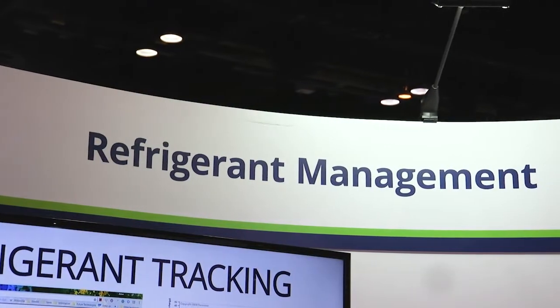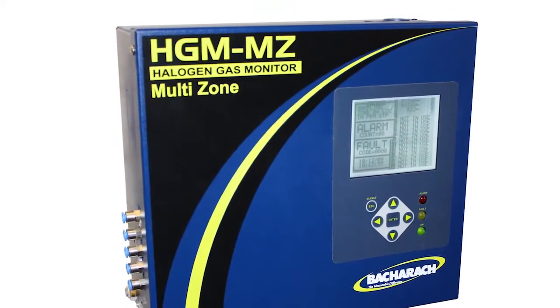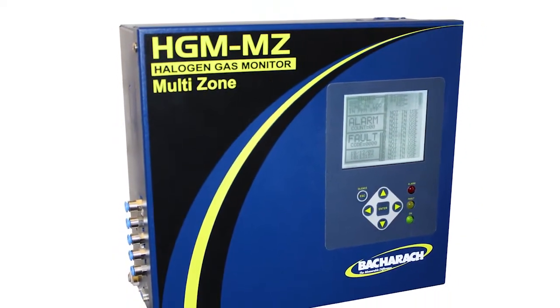I'm Tom Berniston, Bacharach's product manager for our refrigerant leak detection products. I'm here to talk to you about the HGM-MZ. This is our multi-zone refrigerant leak detection product that has the most sensitive detection technology available on the market. We can detect levels as low as 1 ppm. What that really means is you can use this as a tool and a solution to drive a leak reduction strategy within your enterprise.